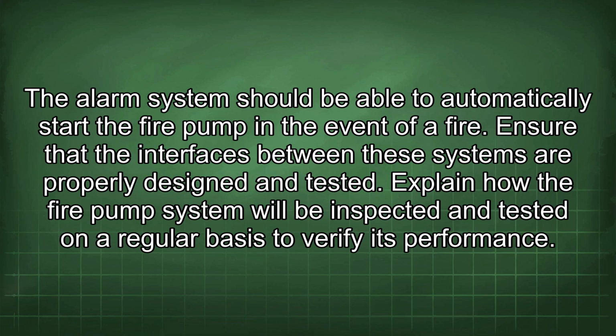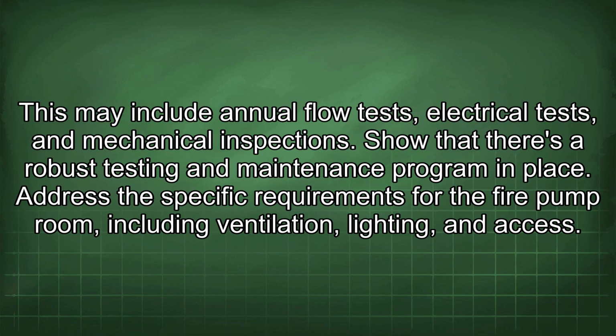Explain how the fire pump system will be inspected and tested on a regular basis to verify its performance. This may include annual flow tests, electrical tests, and mechanical inspections. Show that there's a robust testing and maintenance program in place.